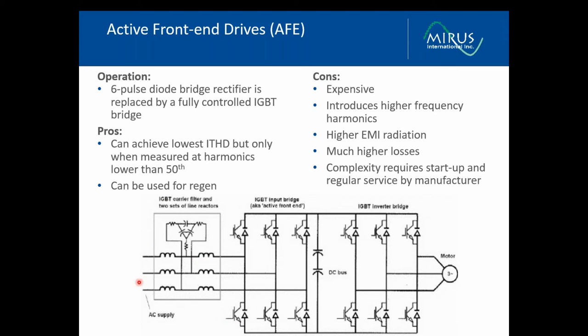But all of these devices require a passive filter in order to deal with the harmonics that they're generating, so these would be equipped with LCL filters as shown here. But again, a passive filter, not unlike the passive filter that would be used on a six-pulse drive system. They're typically smaller and tuned to higher frequencies, but it's the same type of device. The AFEs are quite expensive. They also introduce high-frequency harmonics in a similar manner that the parallel active filters do. It can create EMI radiation. They introduce higher losses and, again, are quite complex, requiring startup and regular service.